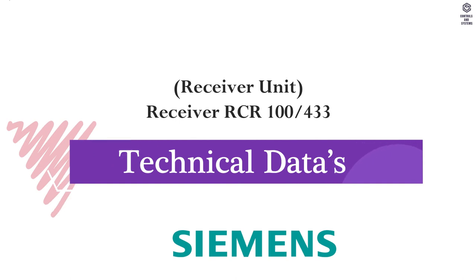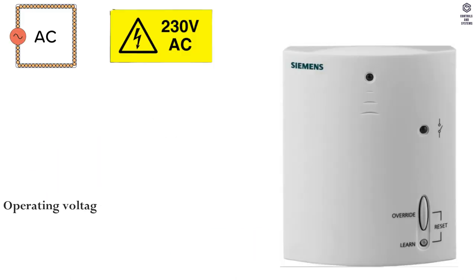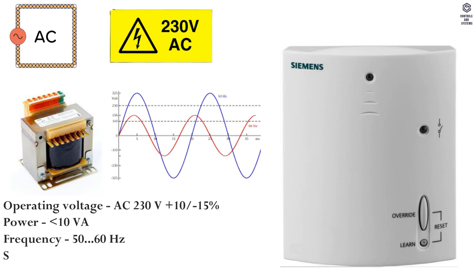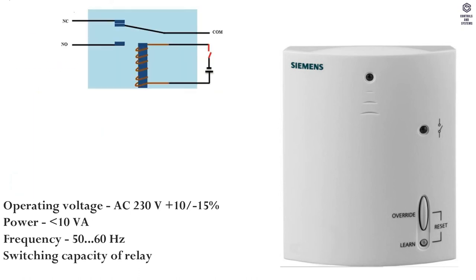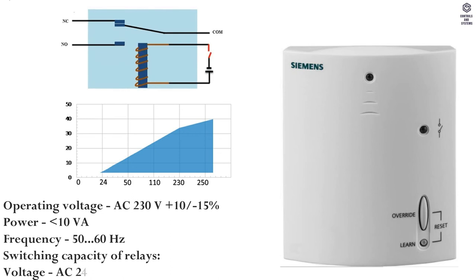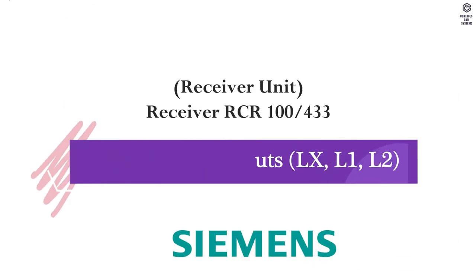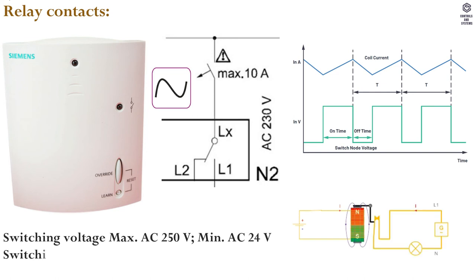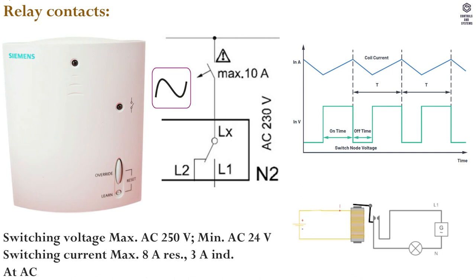Technical data for the receiver unit. Operating voltage is AC 230V +10% / -15%. Power is less than 10 VA. Frequency is 50 or 60 Hz. Switching capacity of relays: voltage AC 24 to 250V; current 8A resistive or 3A inductive. Switching outputs are relay contacts. Switching voltage: maximum AC 250V, minimum AC 24V. Switching current: maximum 8A resistive, 3A inductive.